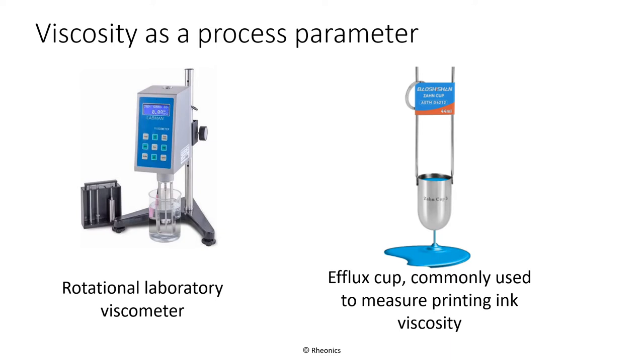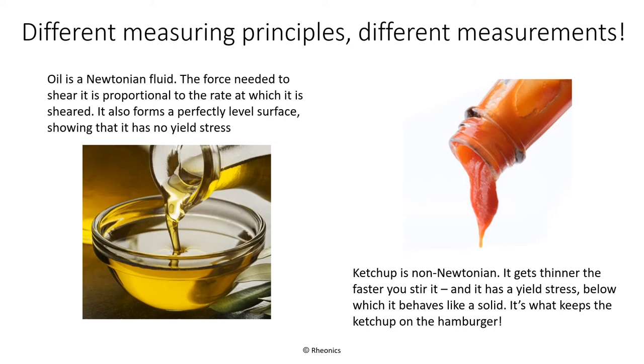There are many ways of measuring viscosity. Traditional lab viscometers either measure the torque the fluid exerts on a rotating spindle, or use efflux cups — often used for printing inks — which are filled with a fluid that drains out of a standard-sized hole. The operator measures the time it takes for the cup to completely drain. Both of these methods require a skilled operator and are time-consuming. The SRV is an inline process viscometer that measures the viscosity of a process fluid as it is flowing through a pipe or being mixed in a tank. It only requires connection to a computer or process controller to make continuous, unattended measurements.